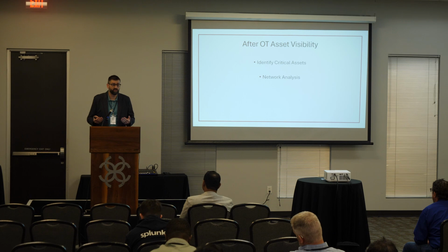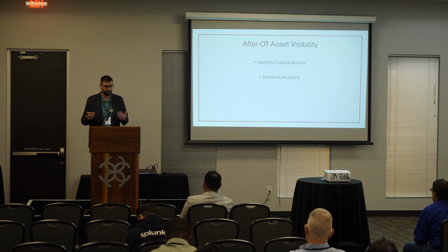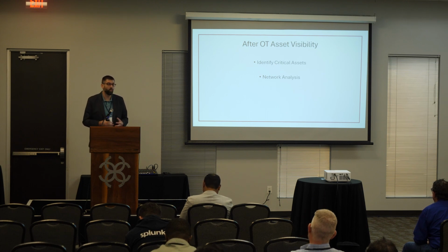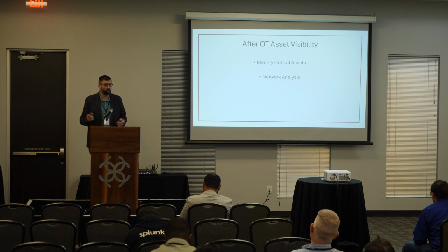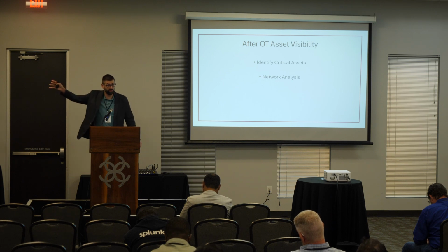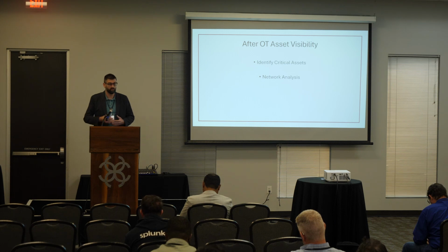We can start doing network analysis. We talked about this a little bit with our passive monitoring, knowing our traffic flows, both the east to west and the north to south traffic flows. Once I can start visualizing that, where are my entry points into the network? Can I lock those down? Can I close down ports? Do I need to even have it open? Where's my east to west flow? We talked about the wastewater plant over here talking to a water plant on the other side of the county. If they have no business talking to each other, let's block them from talking to each other.